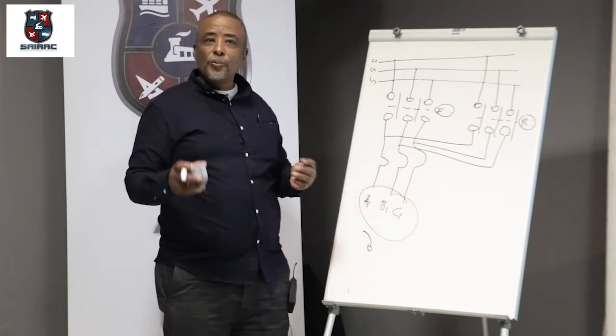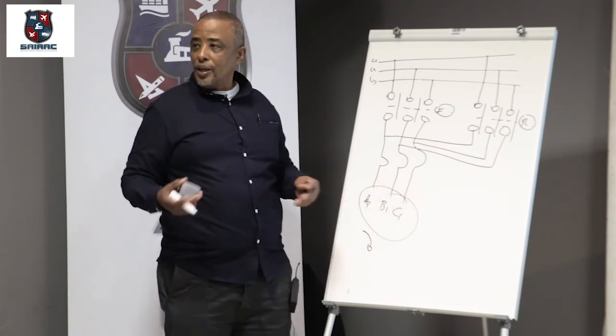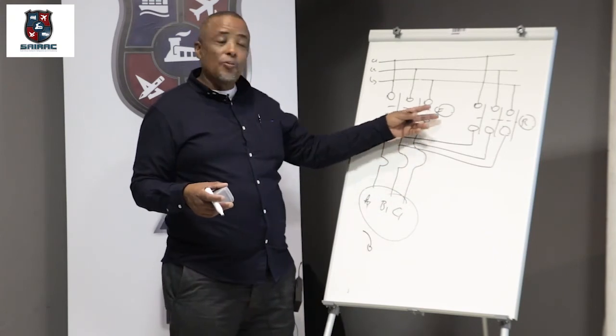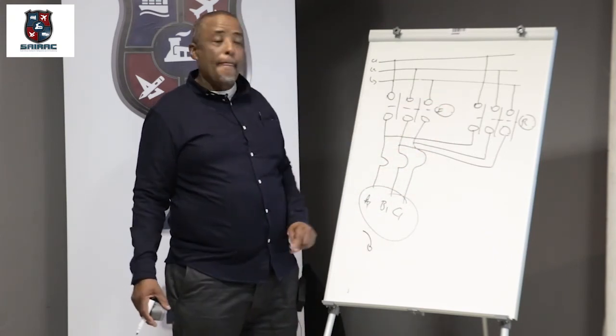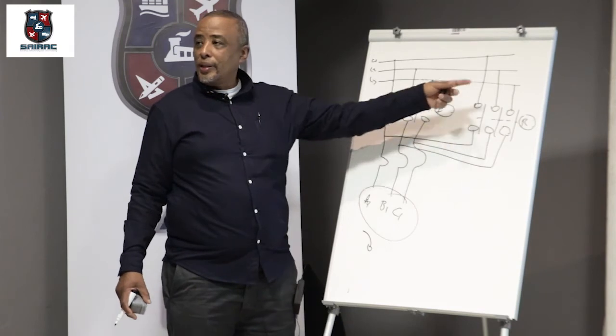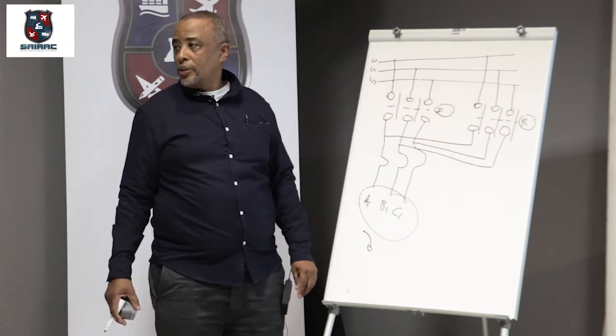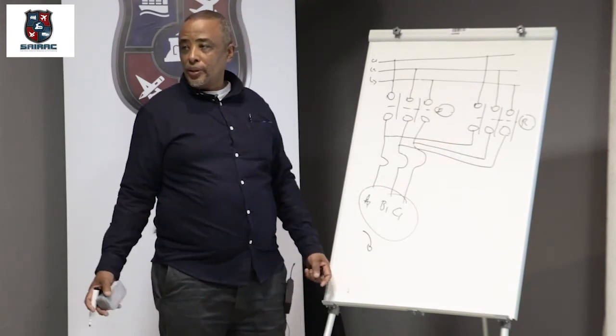Forward, reverse. You program your PLC, inputs, stop, start, outputs. One output could go to your forward coil, and the other output could go to your reverse coil.